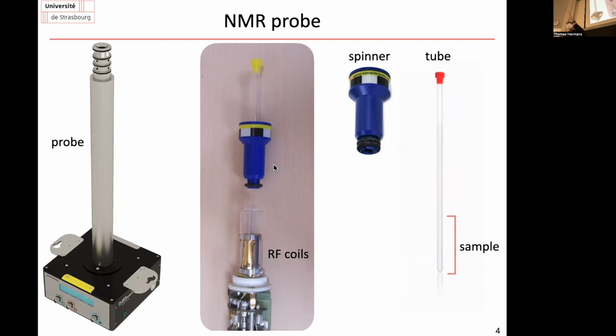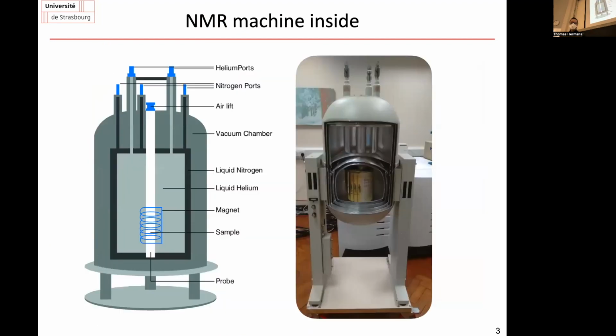You put a beaker, you put the NMR tube, and then slowly over time, the tube bends a tiny little bit. Okay, so it's a slightly bent NMR tube, you put it in the spinner, it descends, and then it doesn't fit into the sample probe here, and then crack, it breaks. Yeah, your tube breaks inside this thing, and then you have a huge mess.